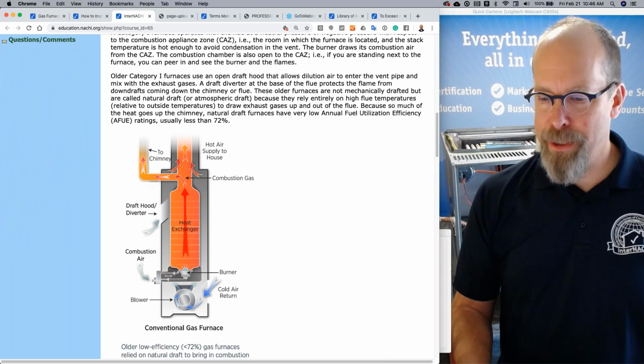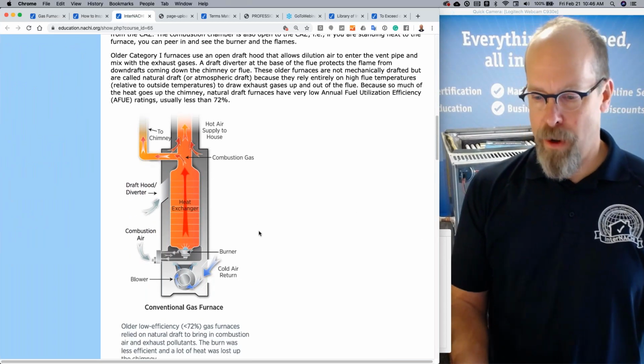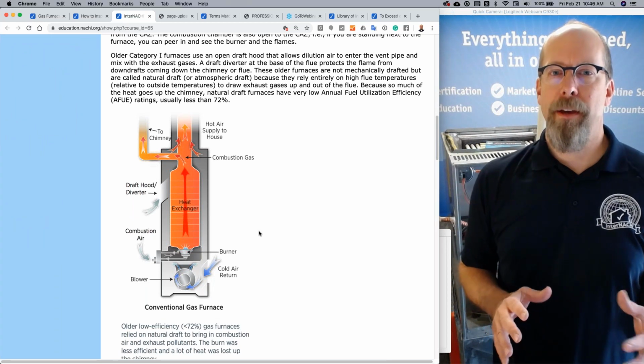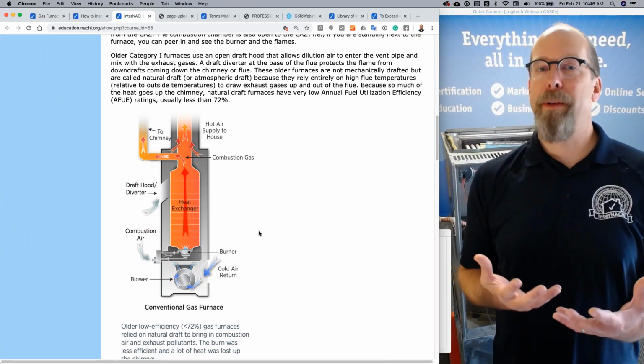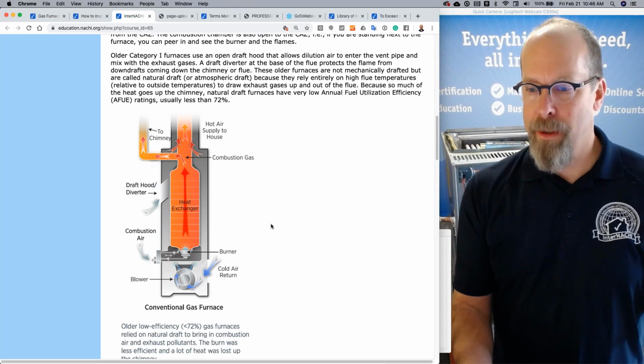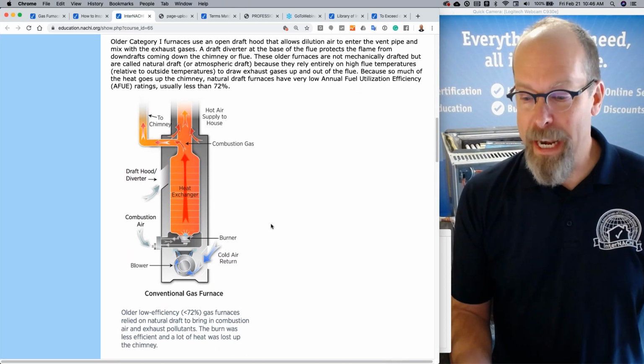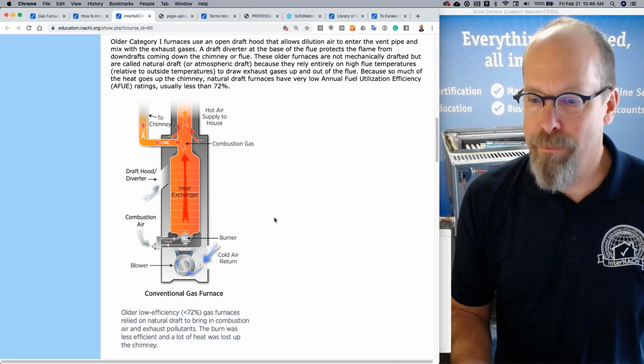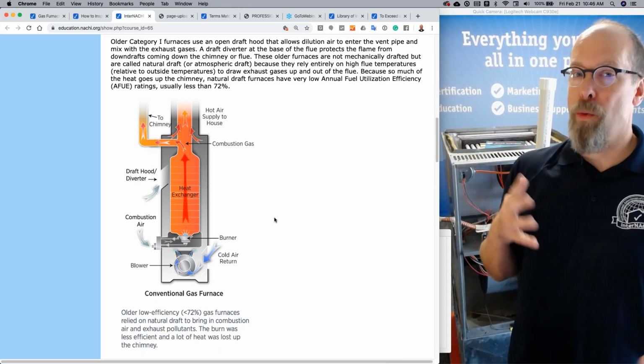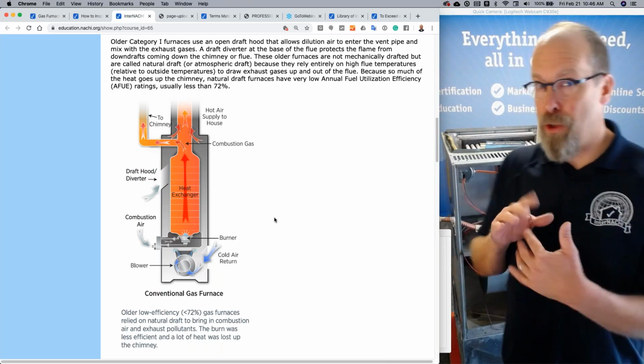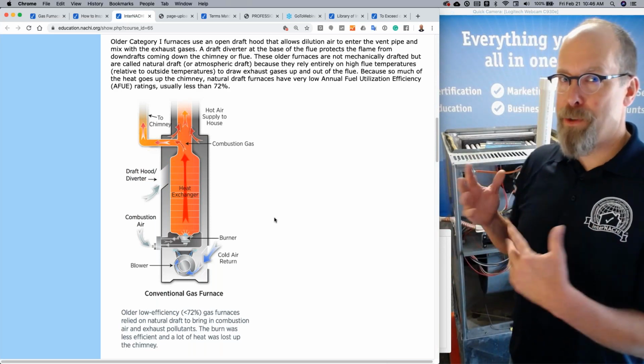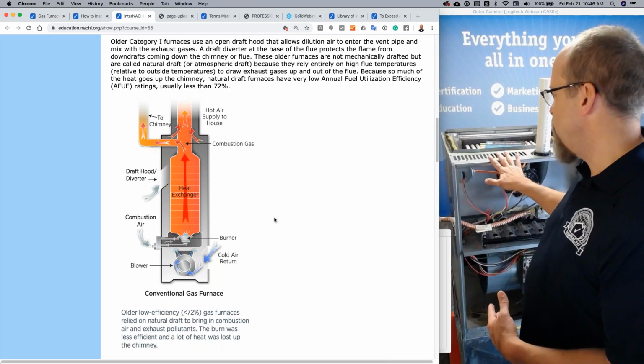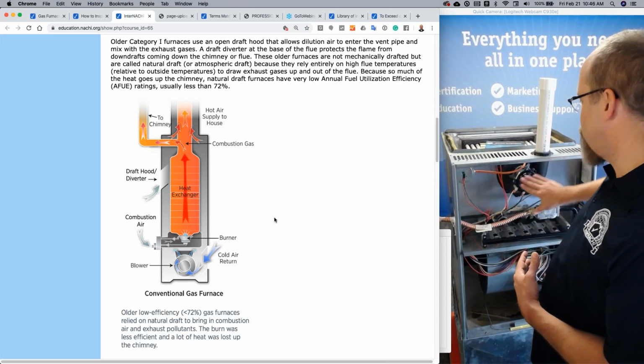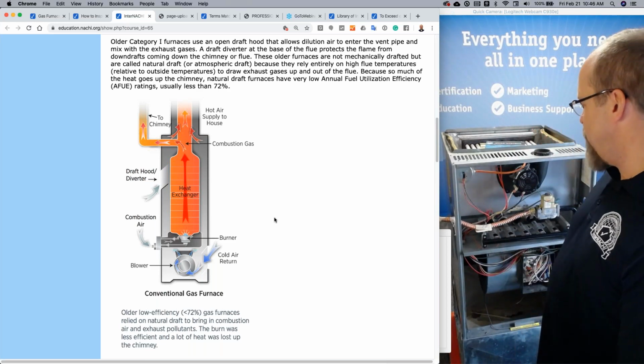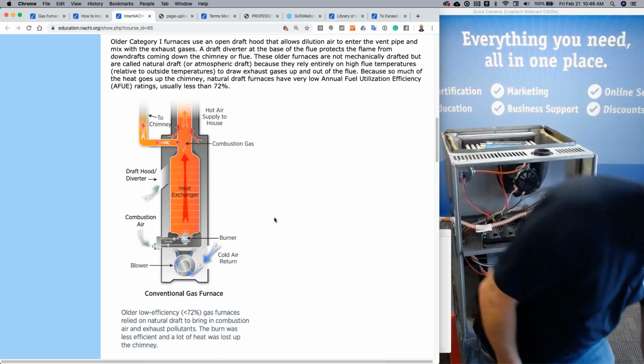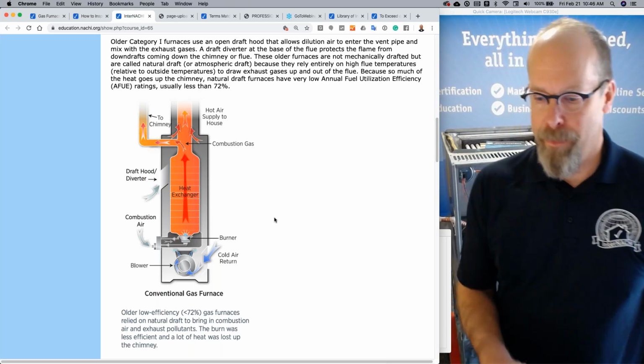And there's a nice illustration of a category 1 furnace, and we're talking low efficiency. It wastes a lot, like 30% of the fuel. So if you come across a natural draft furnace, that's low efficiency. An older one would have that open draft hood that allows that dilution air to enter the vent pipe and mix with the exhaust gases. This is a category 1, newer. It has a draft inducer fan. It needs a metal vent pipe. The burners are open, right? So it's not high efficiency. Category 1.